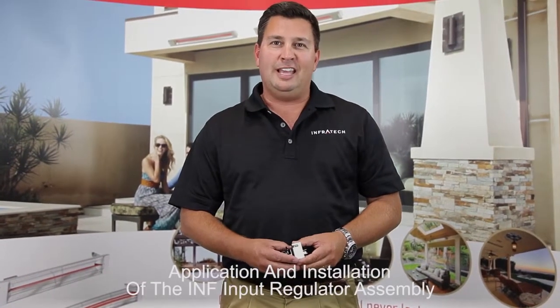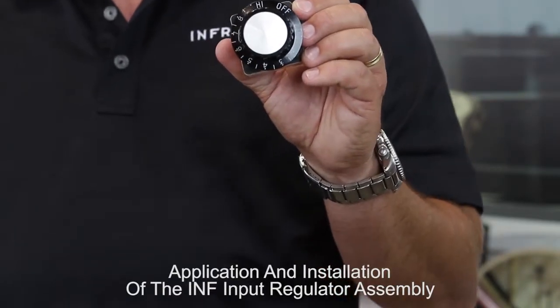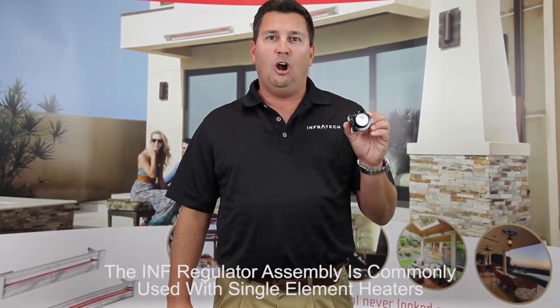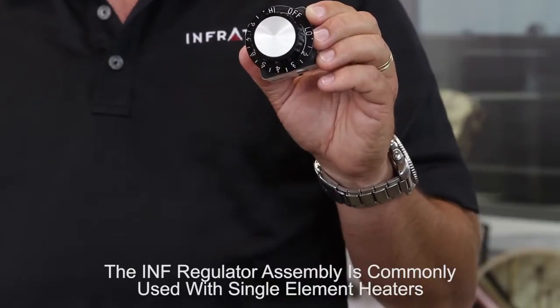In this video, we'll discuss the application and installation of the INF input regulator assemblies. The INF assemblies are used most commonly with single element heaters rated at less than 15 amps — that's typically 3600 watts at 240 volts or 1800 watts at 120 volts.